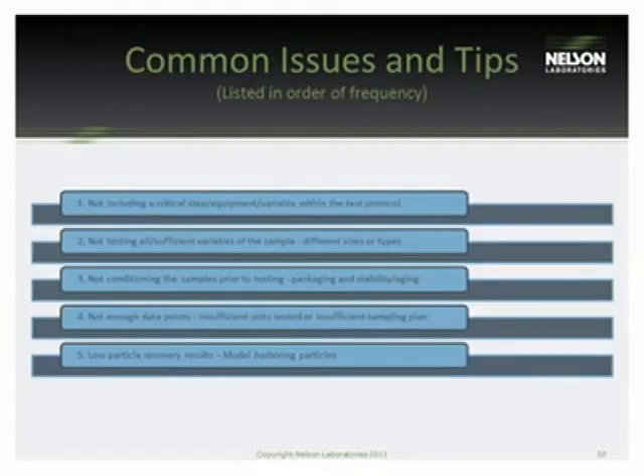And some common issues, these 5 right here probably encompass 90% of the problems that come back to us post-testing when submitting a 510K approval to the FDA. The first is typically not including critical steps or equipment or variables within the test protocol. This is like I discussed in that scenario just before, say there's a certain size or maybe a certain time point that wasn't included in the test or that wasn't tested. That can be significant depending on the situation and the number. Also not testing all the sufficient varieties of the sample if there's different sizes or types. Now it's not necessary to test a great number necessarily.